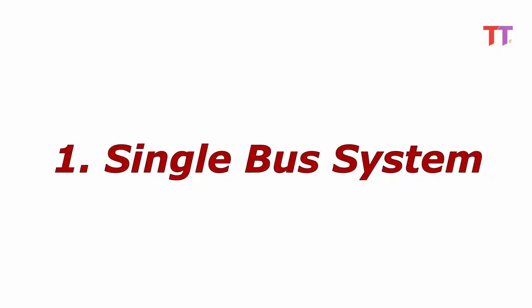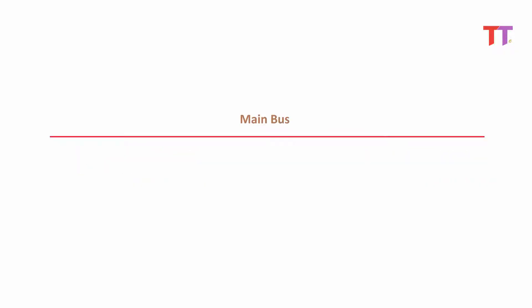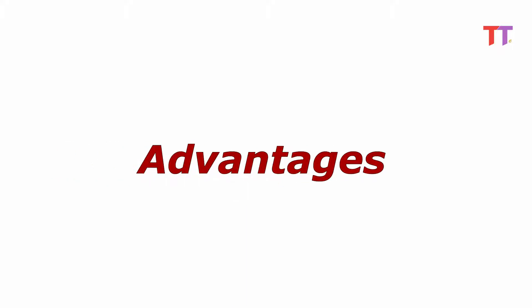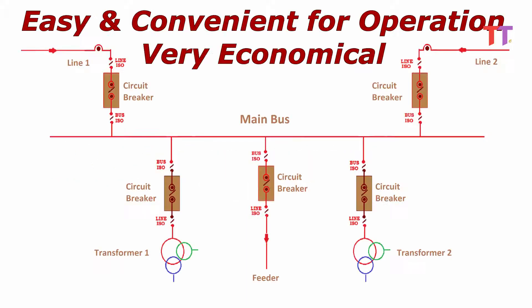1. Single bus system. This is the most basic and simple bus bar system. As we can see in the diagram, in this type all incoming and outgoing bays such as lines, transformers, and feeders are directly connected to a single bus. Advantages of the system: due to its simple design, it is the most easy and convenient for operation. Also, it is very economical because of its least capital cost among all bus bar systems.